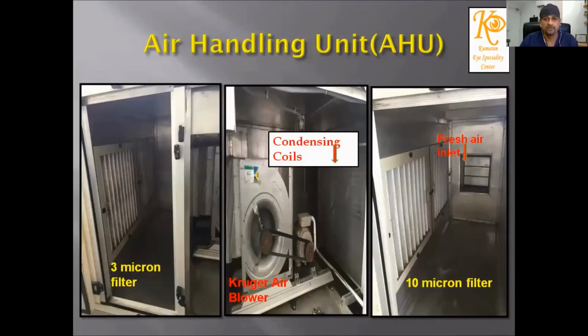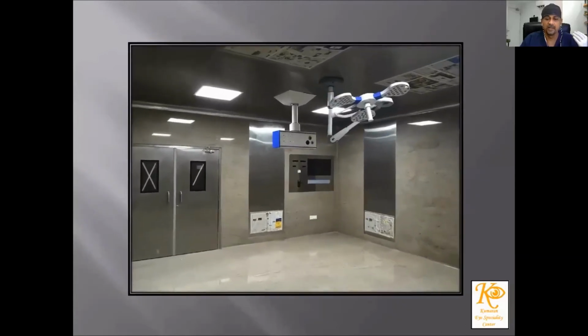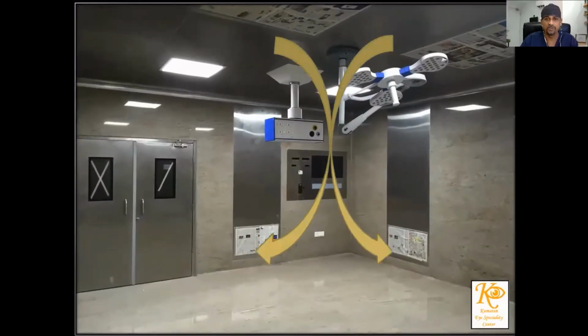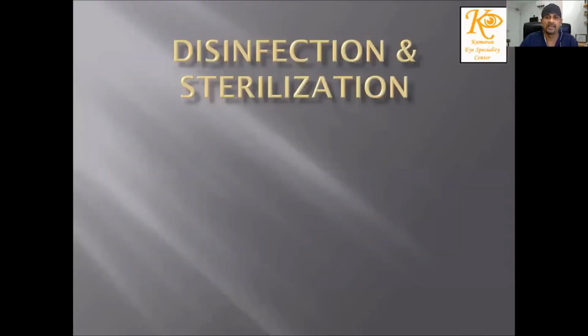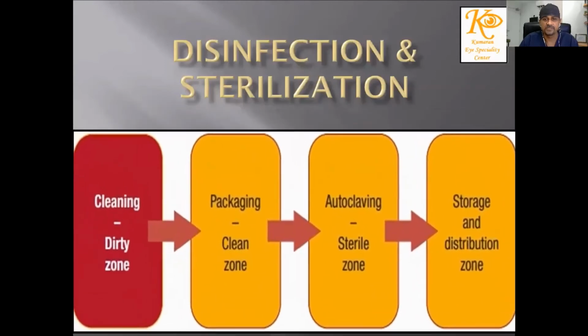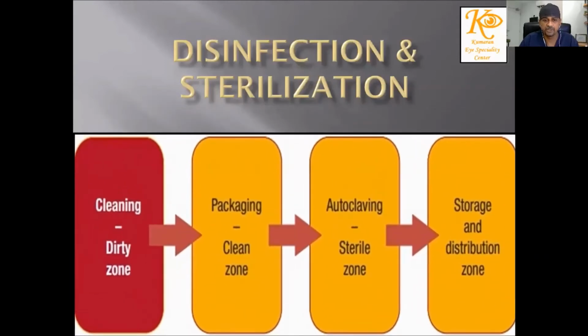The interior of the air handling unit consists of three chambers with two sets of pre-filters and a blower, which cools the air and makes it flow into the theater through the laminar airflow system, which is nothing but a unidirectional flow of air from the ceiling across the room through the table into the return air ducts back into the AHU. The disinfection and sterilization process, the backbone of any surgical unit.